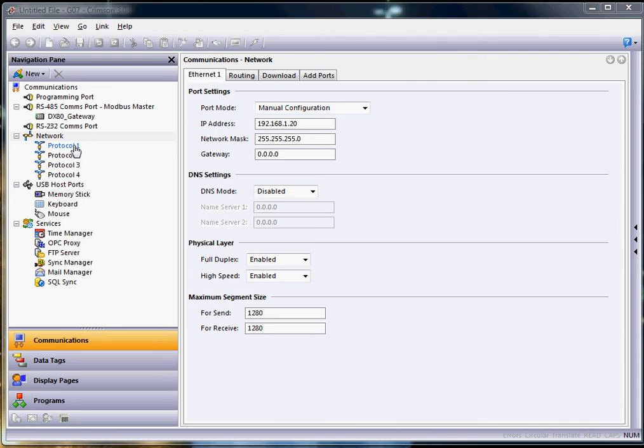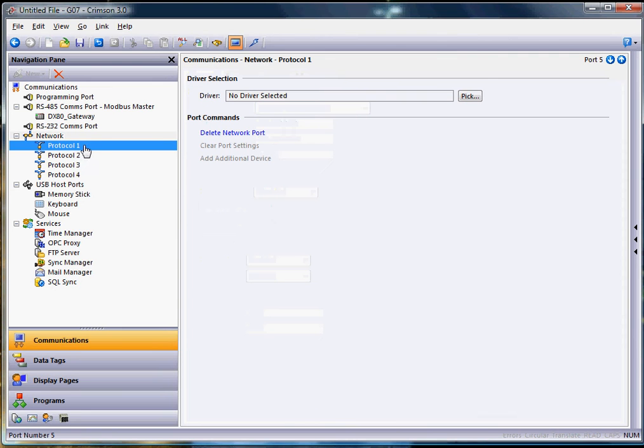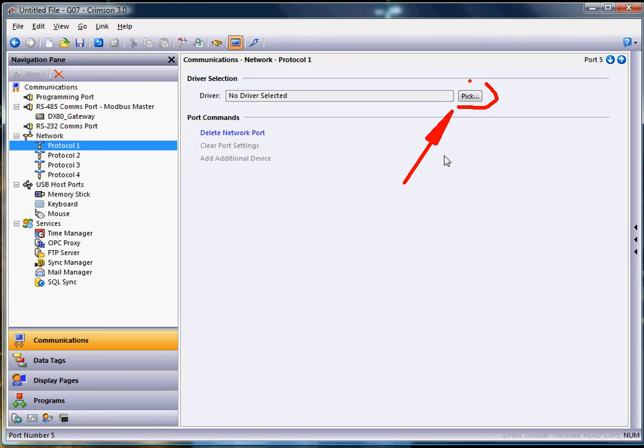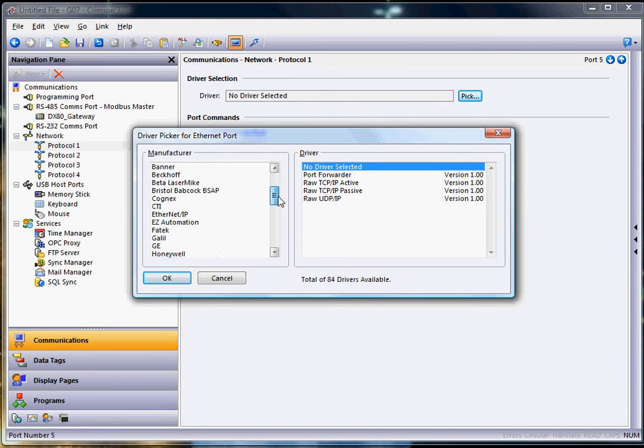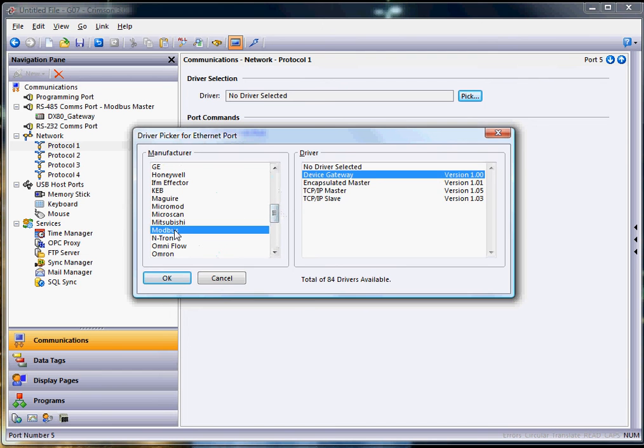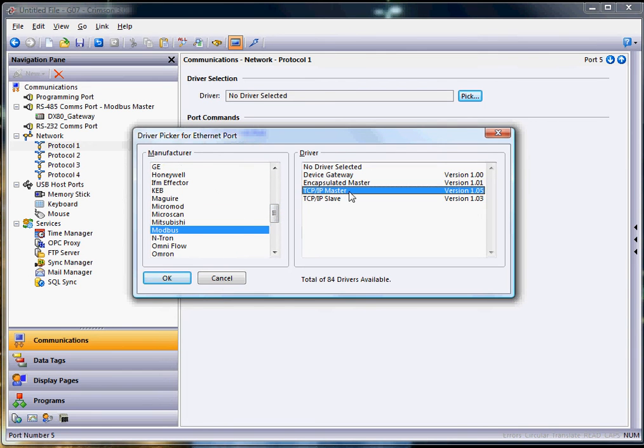Then if I go to protocol number one here, and on protocol number one if I hit the pick button right here, that brings up the listing of the drivers available. Take your little slider bar and slide on down to eventually the word Modbus. Click on Modbus here and we're going to set up the HMI to be the master to talk to the wireless gateway, which is going to be on Modbus TCP. So I'll choose master here and click OK.